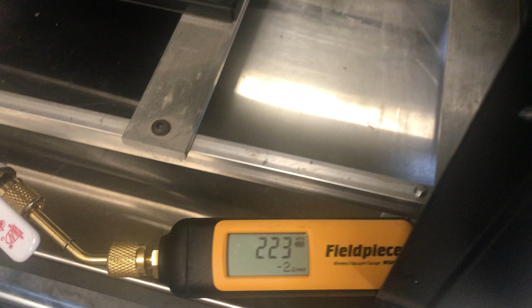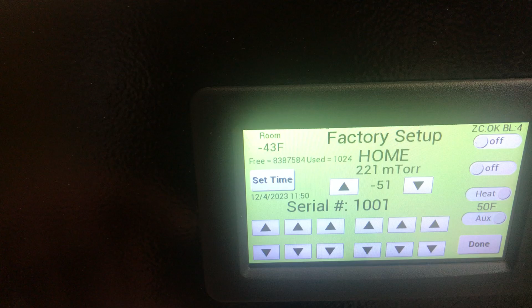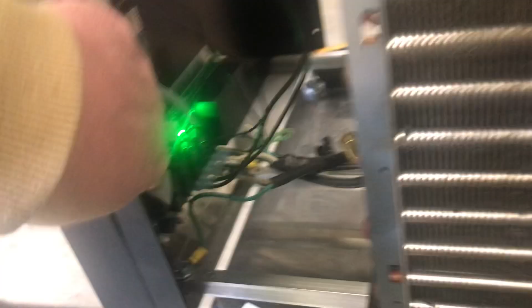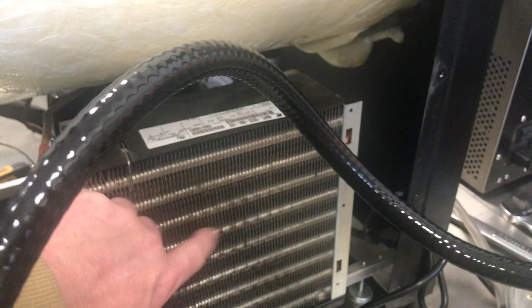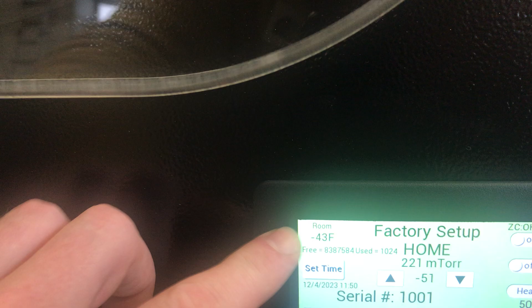on an old machine with a refurbished pump, and it's calibrated pretty darn close. So we're gonna call this a success. I've got to get one more thing for it to be perfect. I've got to add an additional thermistor that I'll put over here to get room temperature. So that'll just connect down in there. That'll connect down here at that plug, and that'll be put up here to get room temperature, and that'll fix that display. But other than that, we're going to call this retrofit a success.